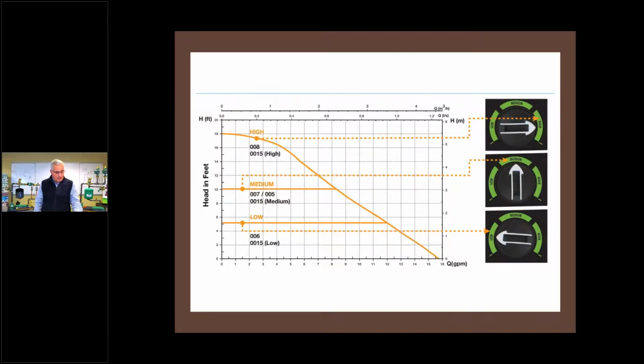That's the red zone. Blue zone, 1.8 at 6. Well, again, we're down here, right about there, 1.8, just past that hash mark. And now I'm at the 6 foot of head mark, which is just above the 5 foot line. So you have a decision to make right now.